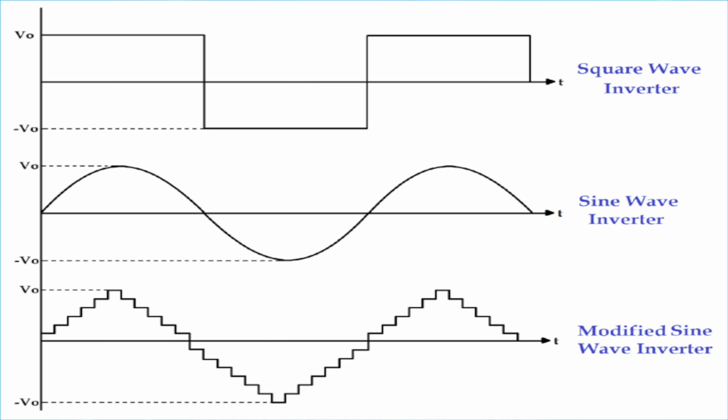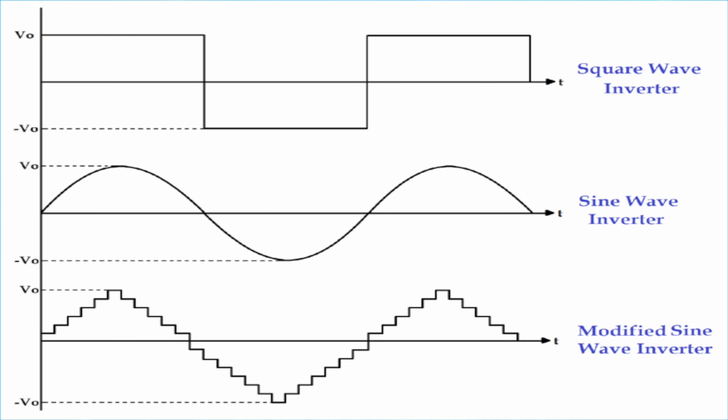The most basic UPS units, which you should probably avoid at all costs, simply create a square wave. The power waveform cycles between up and down sharply at 90-degree angles and should be sufficient for running small power tools and so on, but such UPSs have no place in running sensitive electronics. That's why you want to look for a UPS that has what is known as a sine wave inverter. It recreates the smooth sine wave that you'd see from the utility power.